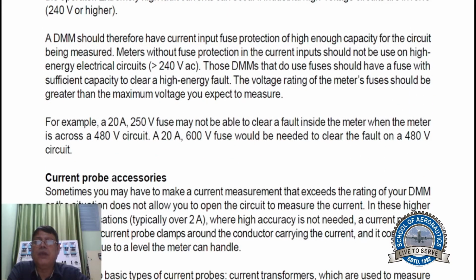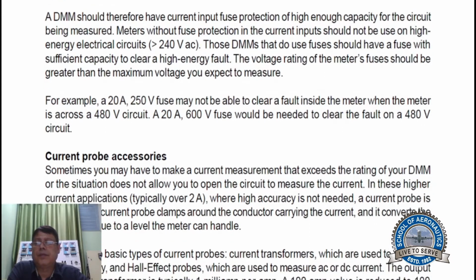A DMM should therefore have current input fuse protection of high enough capacity for the circuit being measured. A meter without fuse protection in the current input should not be used on high energy electrical circuits. Those DMMs that do use a fuse should have a fuse with sufficient capacity to clear a high energy fault. The voltage rating of the meter fuses should be greater than the maximum voltage you expect to measure. For example, a 20 ampere 250 volt fuse may not be able to clear a fault inside the meter when the meter is across a 480 volt circuit. A 20 ampere 600 volt fuse would be needed to clear the fault on a 480 volt circuit.